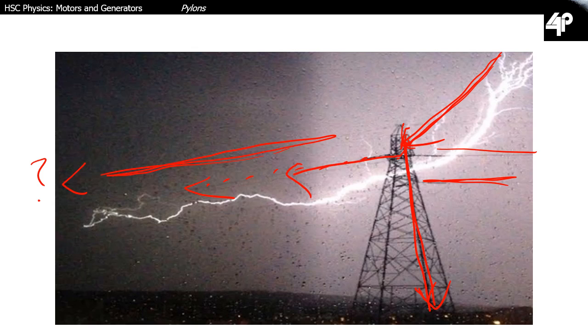Now, a slightly less common scenario here is where the lightning will simply come down and make a direct hit onto the transmission line itself, but this really is the worst case scenario, because once it hits the line, then the lightning is going to be traveling straight down the line and is going to avoid pylons. So essentially you've got the whole lightning bolt heading towards a transformer somewhere further along in the electricity distribution network. Now, at these substations, to protect the transformers, there are certain safety cutout devices there, but they really don't provide a 100% guaranteed protection against lightning damage. And every year there are heaps and heaps of transformers that are permanently knocked out by lightning.